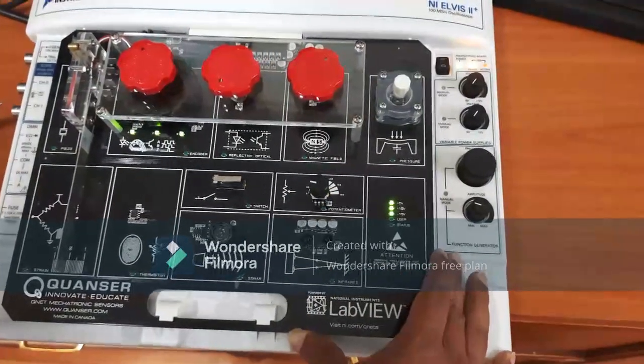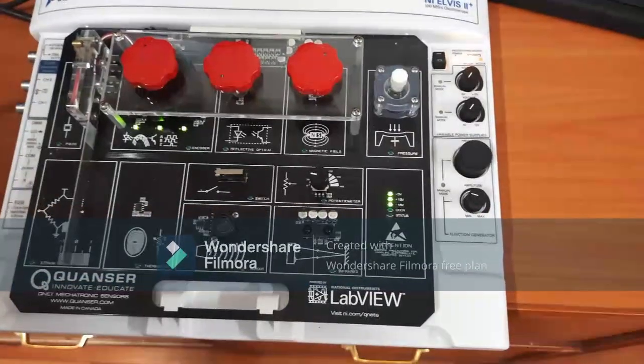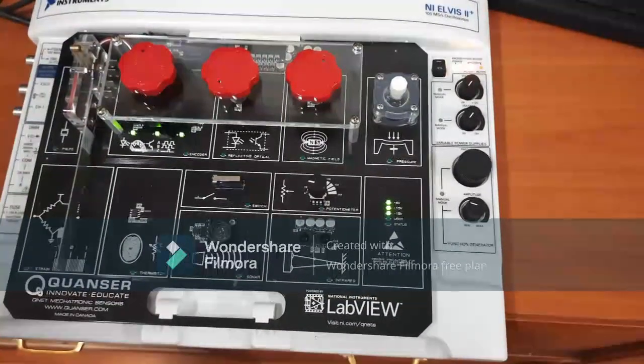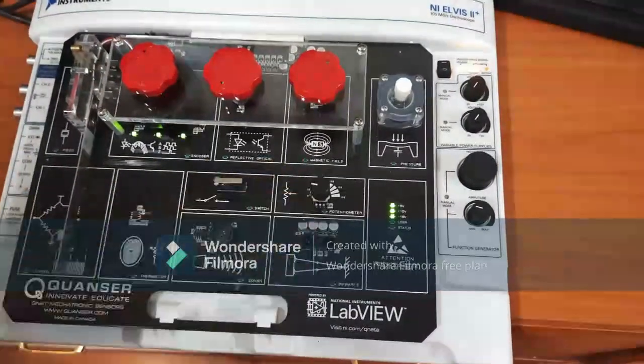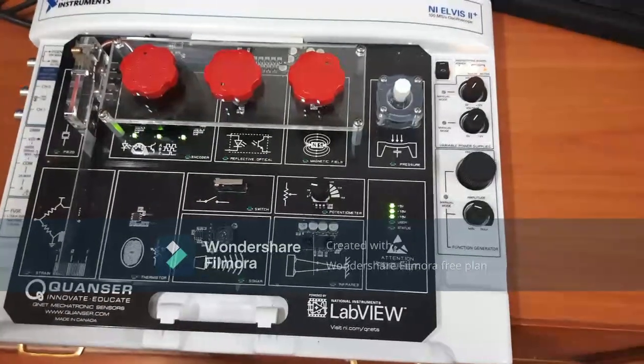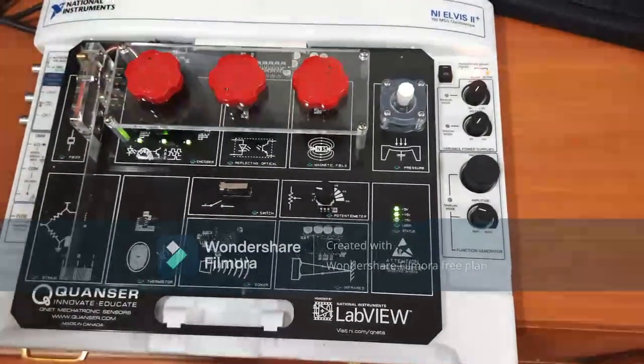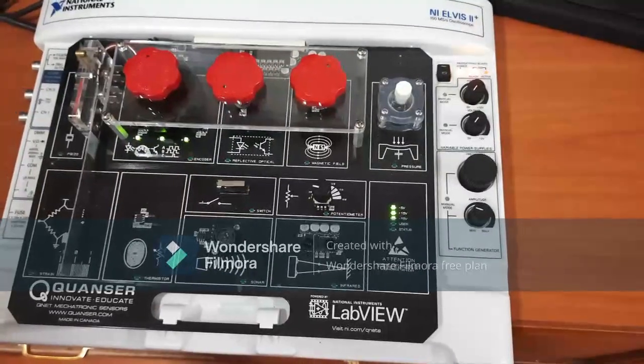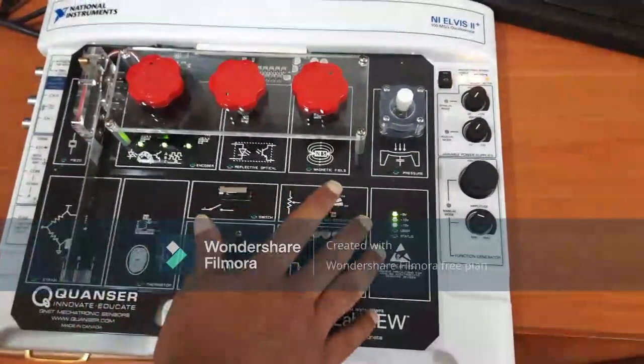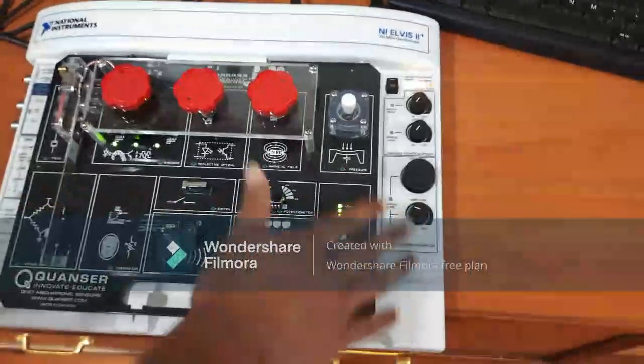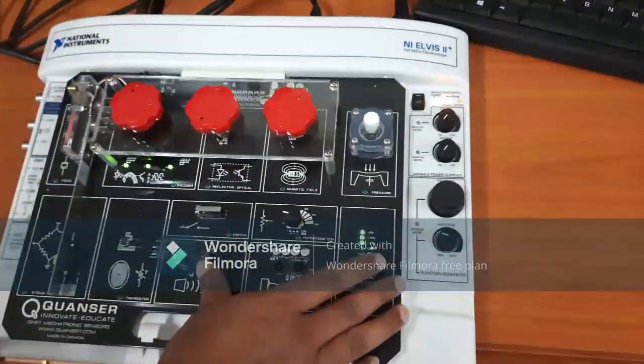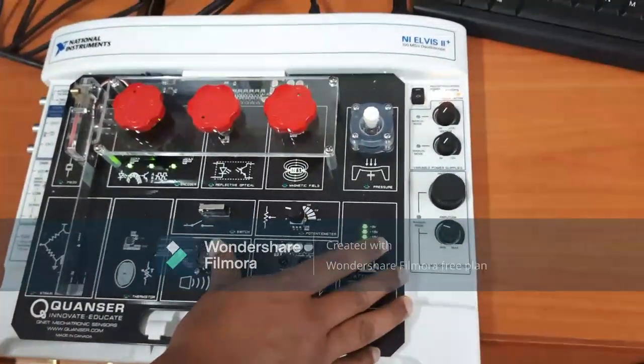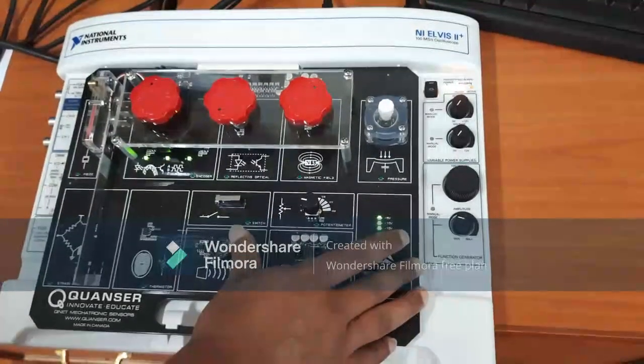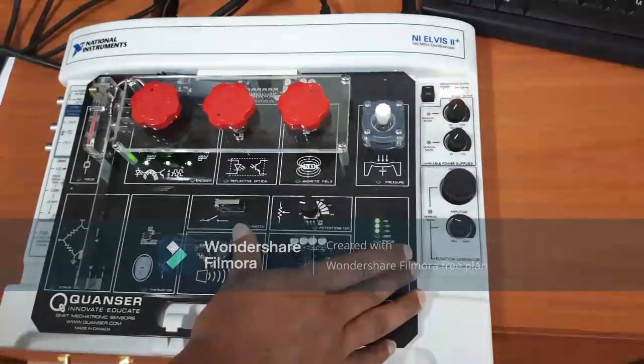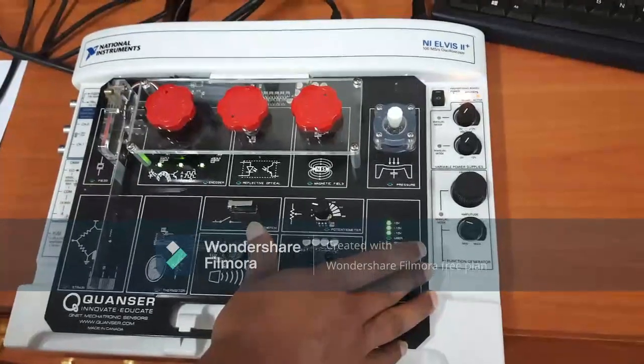Now talking about the offset, it is the deviation from the actual value. Why are we doing all of this? Because this sensor is not calibrated. So that is the part where we get the data. After getting the data, with the software value and the corresponding value, it will automatically show me the offset value, how much the deviation is. Once I know the deviation, I will do the calibration and get the output data.